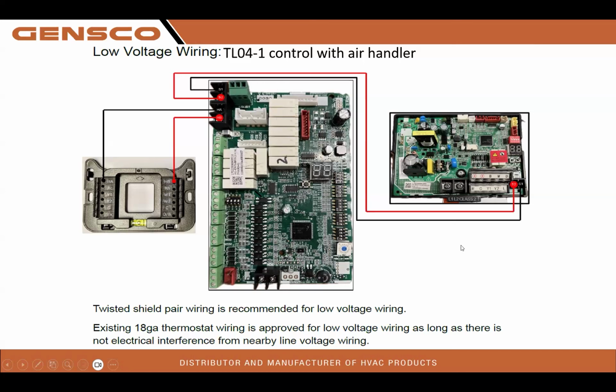We do not need to use 18-gauge stranded shielded wire. We can use standard 18-gauge solid wire. It is approved. We have had 0 communication issues using 18-gauge solid wire. But I do not want you using the old Cat5 cable that you would see on some of the Coleman equipment. Let's stay 18-gauge.